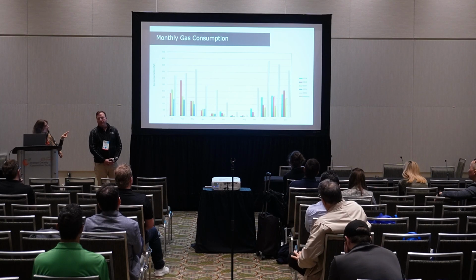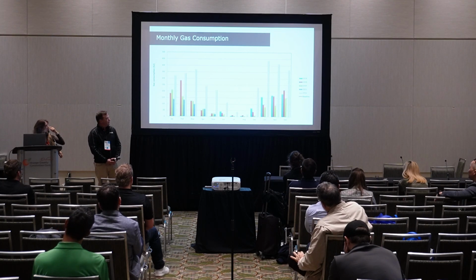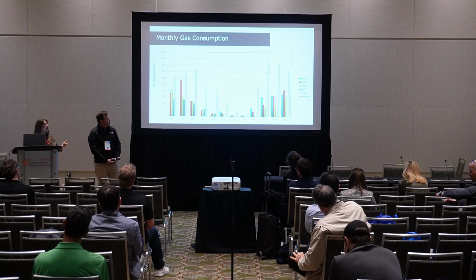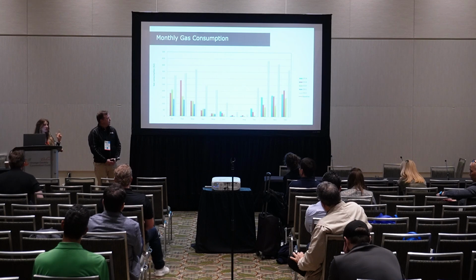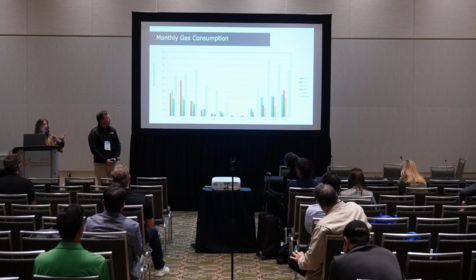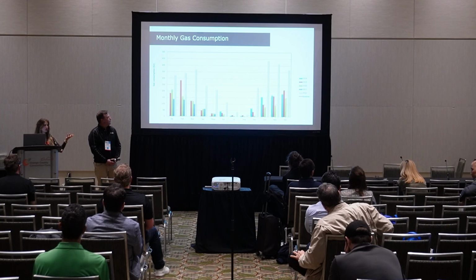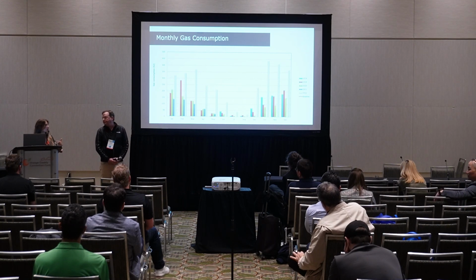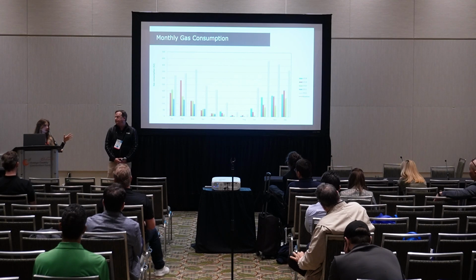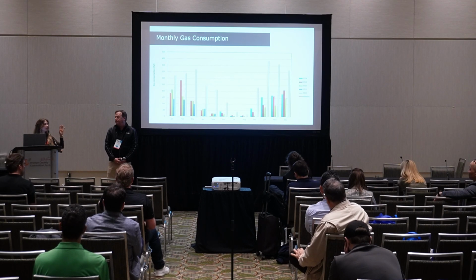But just looking at that data, what happened here is they had a building automation system provider, and they switched partway through, so they did a switchover of the system. This big heat recovery chiller they had was not properly commissioned as part of that setup, so now the gas boilers became the main source of heat. They were paying for this $2 million heat recovery chiller that was basically idle for a year, and now they're paying all this gas. This whole year they weren't meeting their performance targets, and nobody knew until we came in to do an energy study.